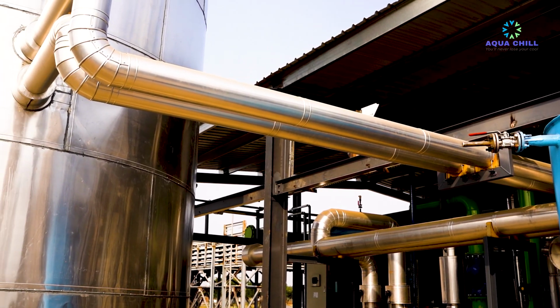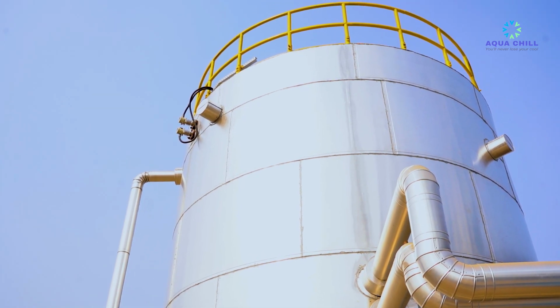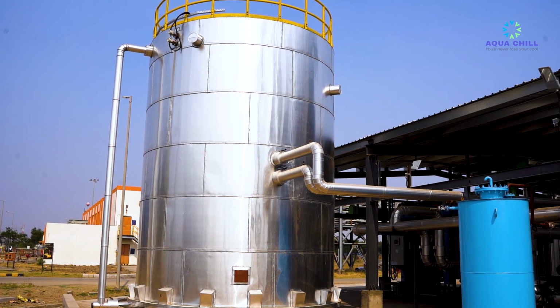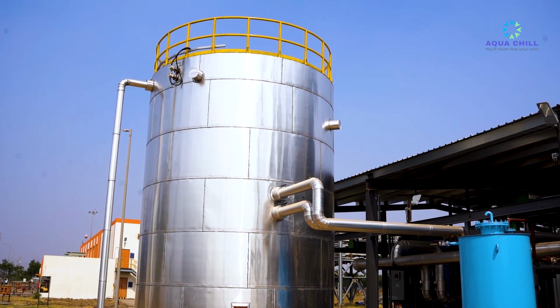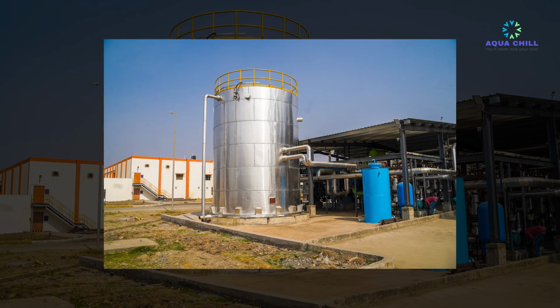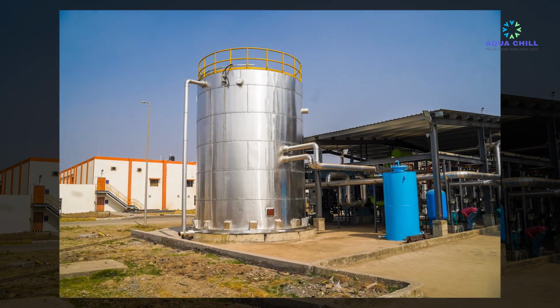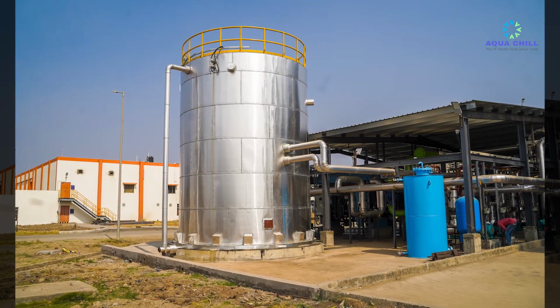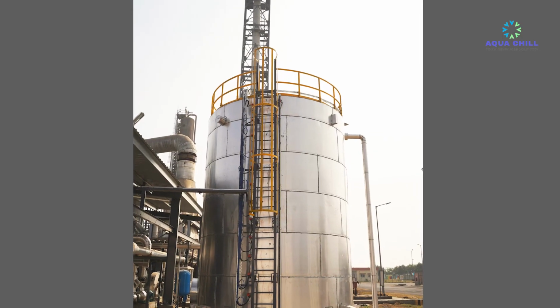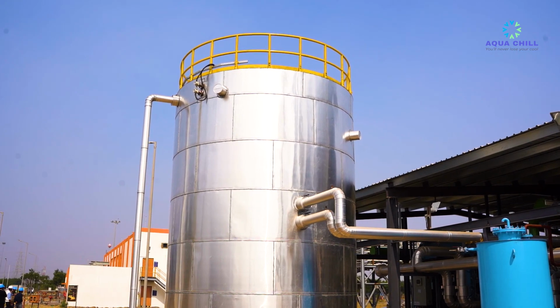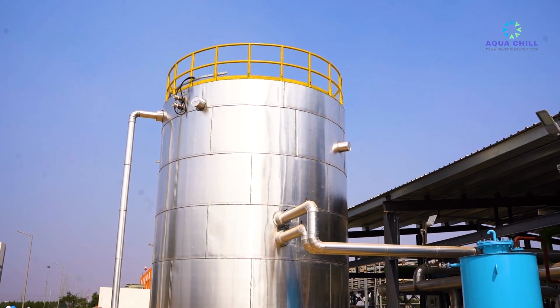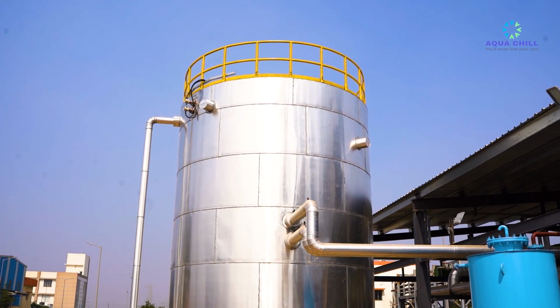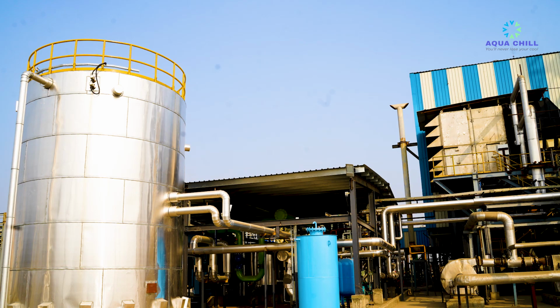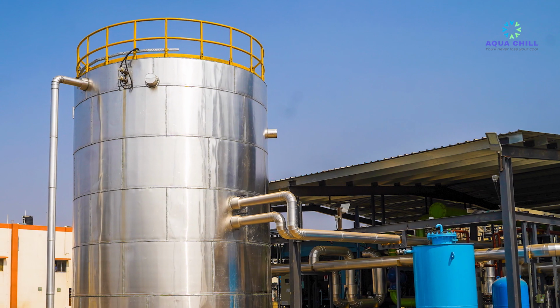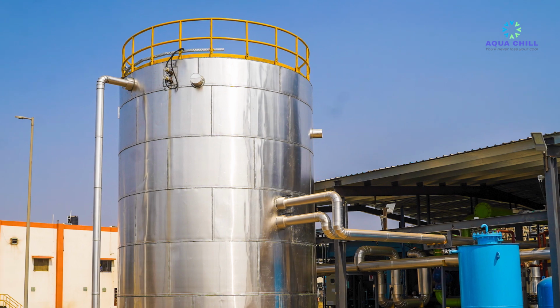The thermal flywheel involves storing cold energy in the form of water, unlike the routine techniques of using ice phase change material. Chilled water is stored in a tank in such a way that the cold water layer remains under warm water without any physical separation. This is achieved by using the difference in the buoyancy of water at different temperatures. This has helped in reducing the size of the absorption chiller by approximately 30%, making it just right for the steam available from the recovery project.